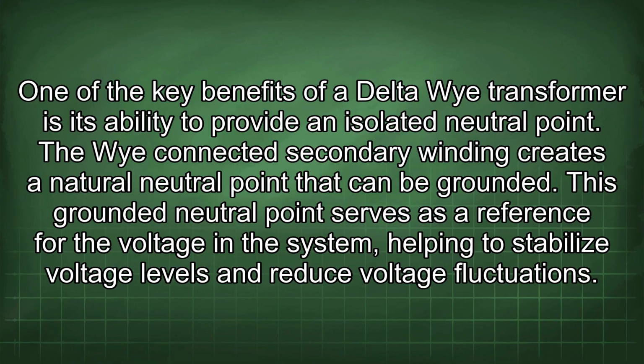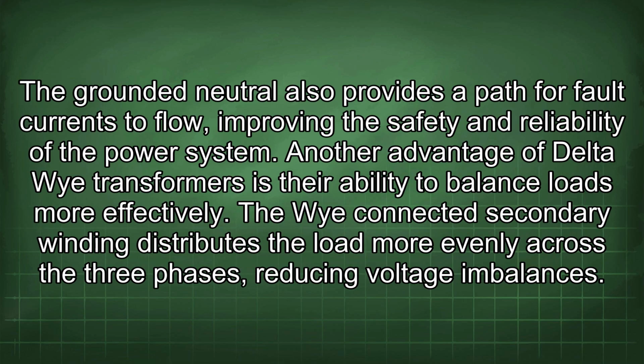The Y-connected secondary winding creates a natural neutral point that can be grounded. This grounded neutral point serves as a reference for the voltage in the system, helping to stabilize voltage levels and reduce voltage fluctuations. The grounded neutral also provides a path for fault currents to flow, improving the safety and reliability of the power system.